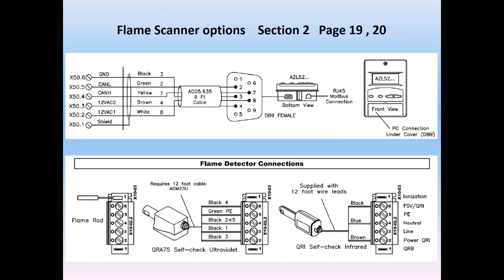Also detailed in technical instructions is the pinout of the pre-made AZL cable, part number AGG5.635. This is to assist in troubleshooting. Note the AZL's three ports: a DB9 on the bottom of the AZL for CAN bus, also on the bottom an RJ45 RS232 Modbus RTU connection for the BMS, and thirdly, on the front of the AZL behind a closed door, a DB9 for connection to an optional PC for backup and restore.